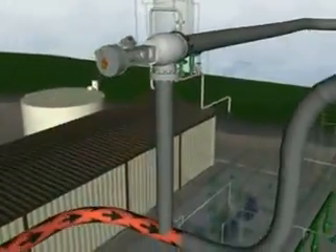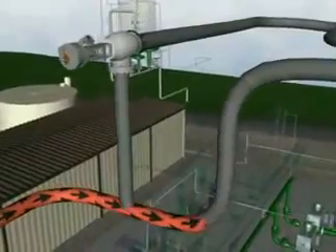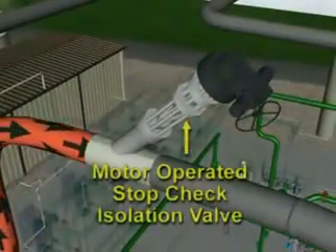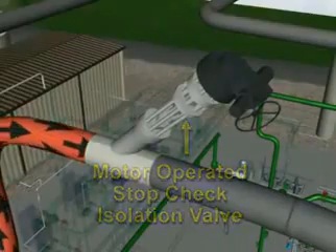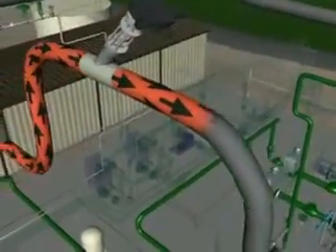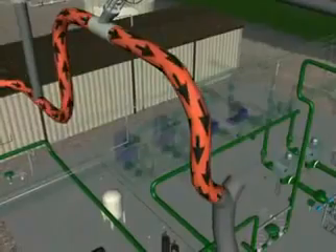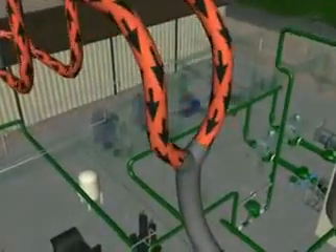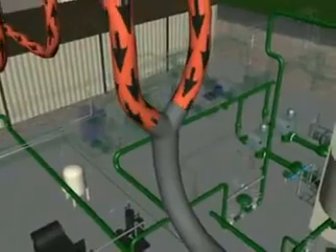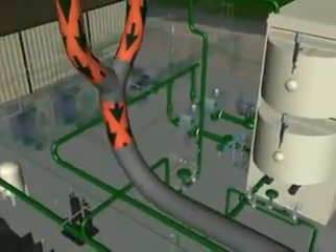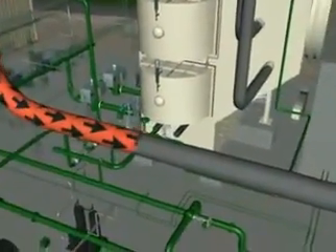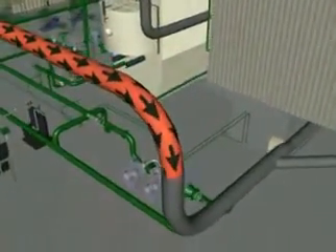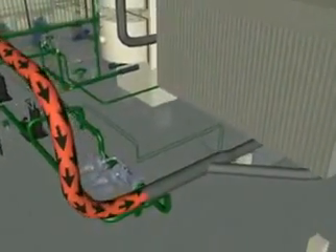When the steam turbine is capable of accepting hot reheat steam, the steam passes from the condenser bypass valve intersection to the hot reheat steam stop check isolation valve. Downstream of the stop check isolation valve, the hot reheat piping combines with the other HRSG reheat discharge and continues as a single pipe to the steam turbine area. This piping arrangement allows the hot reheat from both HRSGs to combine as a single hot reheat steam source to the turbine.